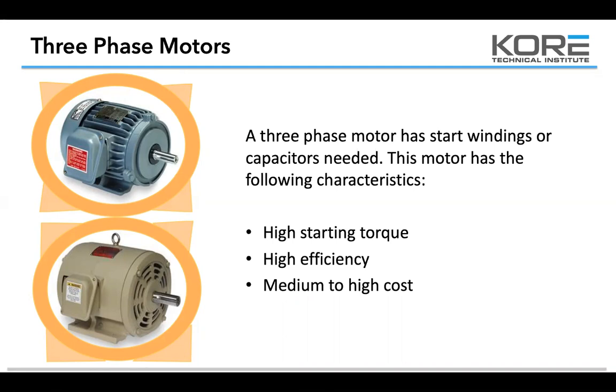Also, the nice thing about a lot of these three-phase motors is these larger ones. What we're looking at right here, you see that top one where it has the back shroud and then it's got the ribbed body. That's an air-cooled motor. It's got a fan blade on the back that actually cools that motor as the rotor turns. As that rotor spins, it spins that fan blade on the back, and then that fan blade cools that motor through that shroud. It pulls air in through the backside of the motor and cools the body of the motor. And this other one is where you see the holes in the motor itself. It's drawing air through the motor to cool the windings. It's an open winding. So this one's an enclosed and that one's an open.